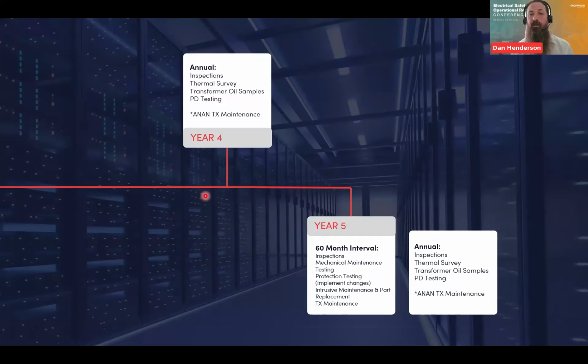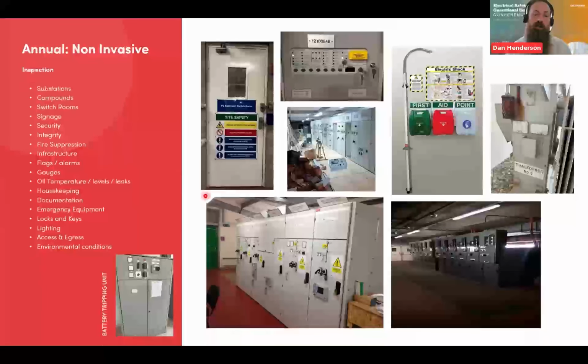So what I would typically do is afterwards, this is really intrusive. You're disconnecting things, you're reconnecting things, and obviously you're putting it all back, and the integrity should be good. But there are occasions where you have altered or adjusted systems. So it's good to have a baseline, so when you follow it up and do another PD survey or a thermal survey, you can compare those baseline results to the results now to make sure you haven't had any significant change. So we're just going to go into the annual items, which should be non-invasive, so it shouldn't require any downtime.